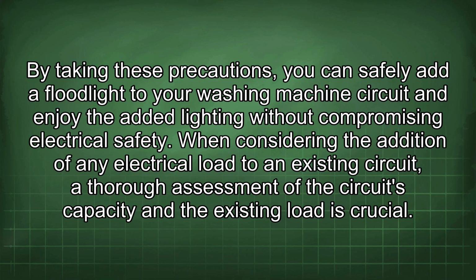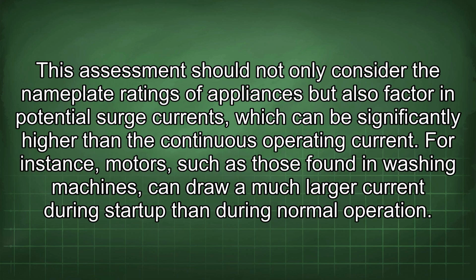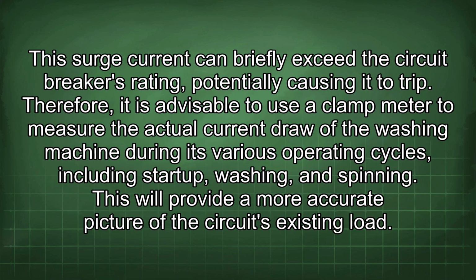When considering the addition of any electrical load to an existing circuit, a thorough assessment of the circuit's capacity and the existing load is crucial. This assessment should not only consider the nameplate ratings of appliances but also factor in potential surge currents, which can be significantly higher than the continuous operating current. For instance, motors, such as those found in washing machines, can draw a much larger current during startup than during normal operation. This surge current can briefly exceed the circuit breaker's rating, potentially causing it to trip.